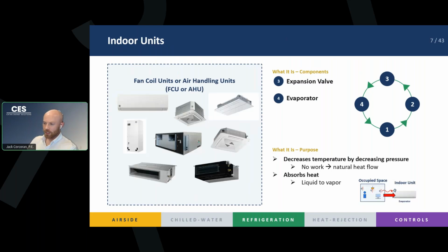Our indoor units are called fan coil units or air handling units, our FCUs and our AHUs. As I said, some of them can be ducted and some are not ducted, but essentially they all have fans to move the air and they all have a coil with the refrigerant in them. Talking about the refrigeration cycle, these are components 3 and 4, right? This has our expansion valve, where we are decreasing our pressure, and it has the evaporator, where we are evaporating our liquid into vapor and transferring the heat. These all sit in our occupied space as well.